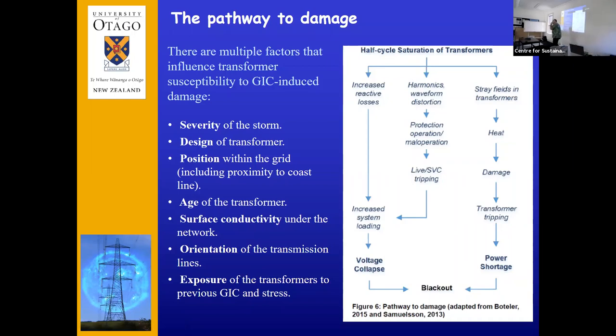This sort of space weather effect produces geomagnetically induced currents - that's what those currents are called. The space weather risk to a power grid is clearly a global thing; it starts with the sun slapping the earth and starting global-level processes. But most of the pathways to damage depend on local issues - which way our power lines run, what our ground is like - so it needs to be solved at a regional or national level. It needs to be considered. For some countries, the answer may be that it's not really a big deal; for others, it clearly is, and it needs to be considered locally.